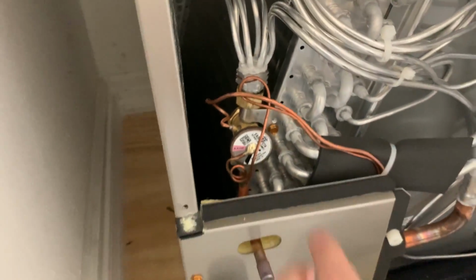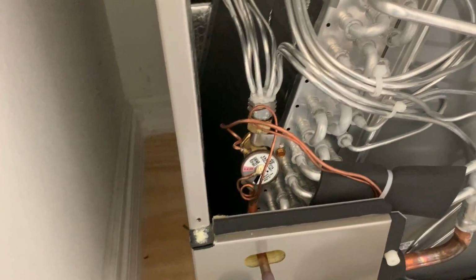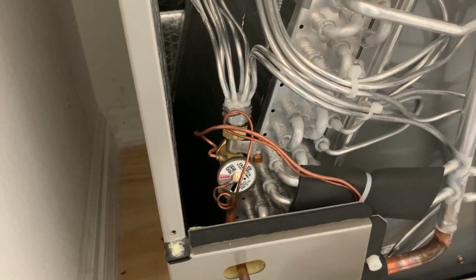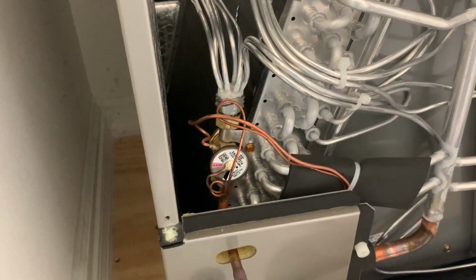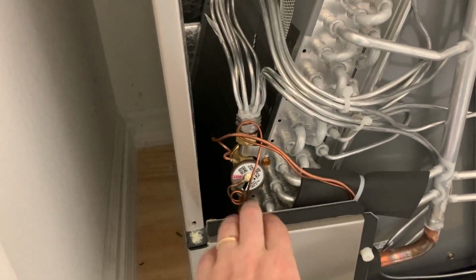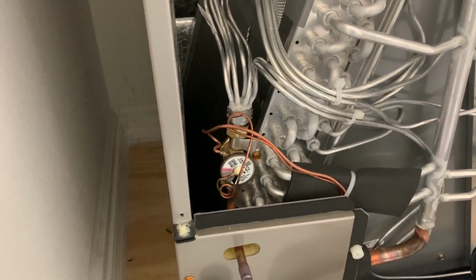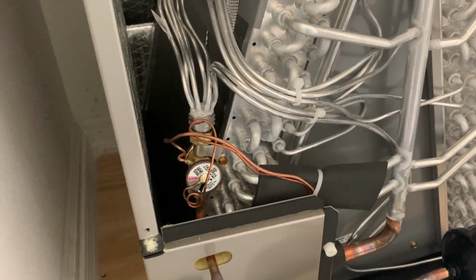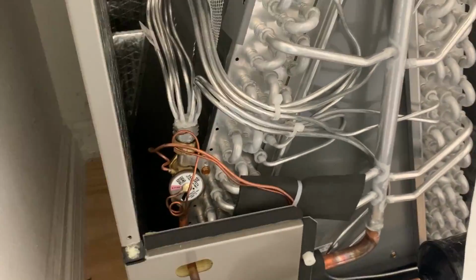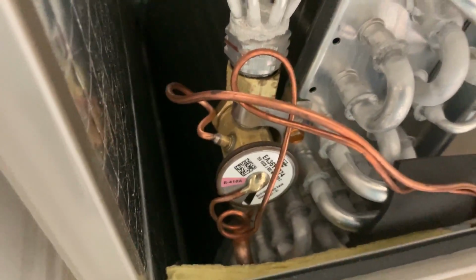One thing interesting with Carrier is they still do use thermostatic expansion valves rather than electronic expansion valves, and they do function the same way. I mean, in both cases, the job of the expansion valve, whether electronic or thermostatic, is to maintain evaporator superheat, and so it still does a good job at that, but it is one thing that's a little unique with these units.